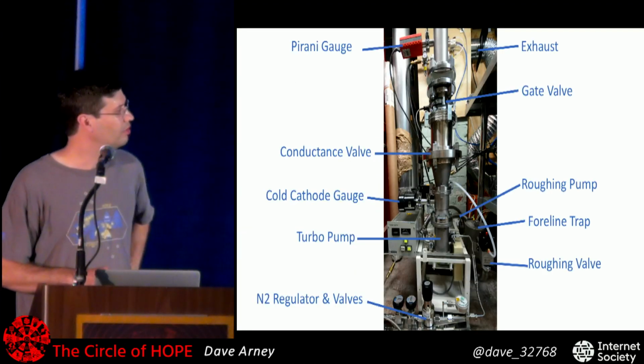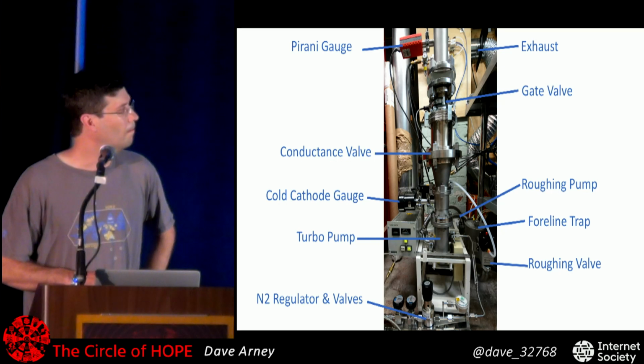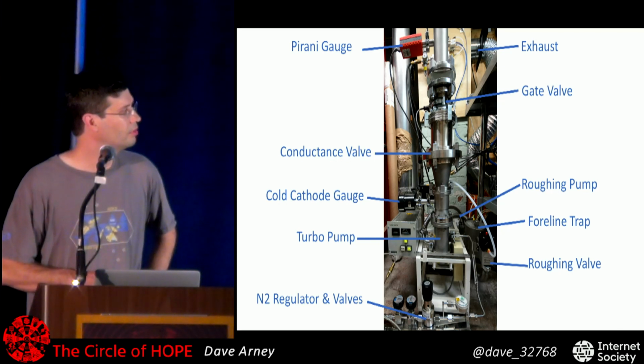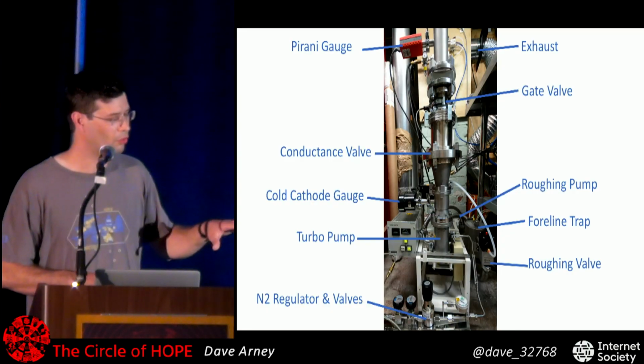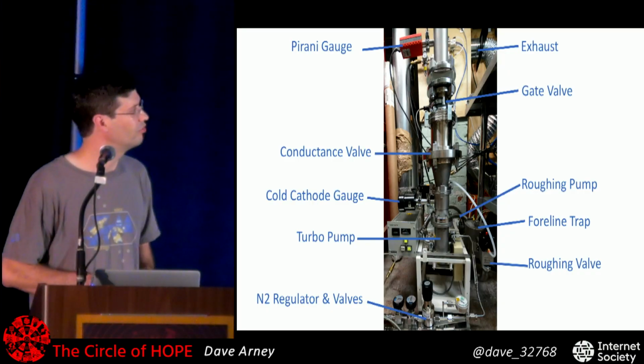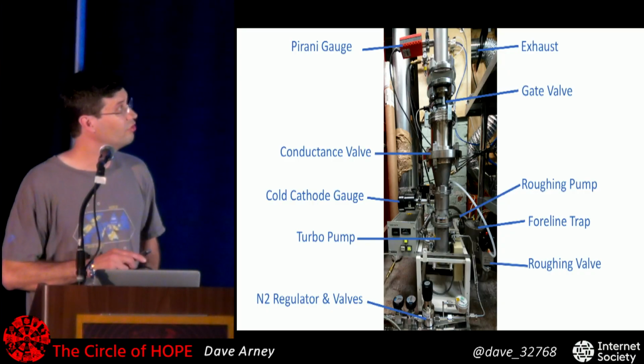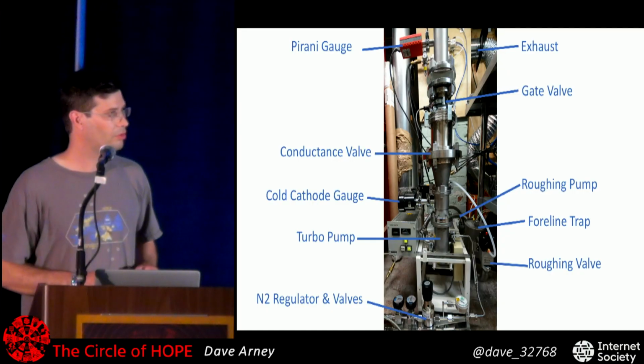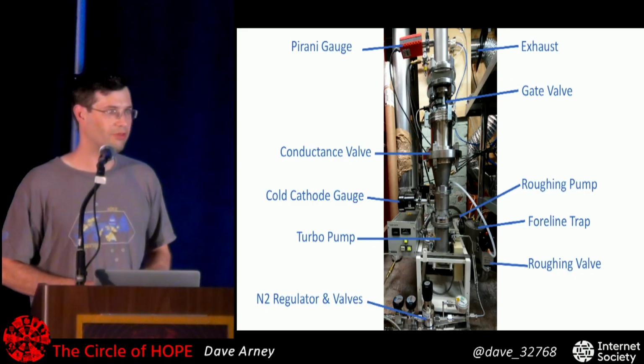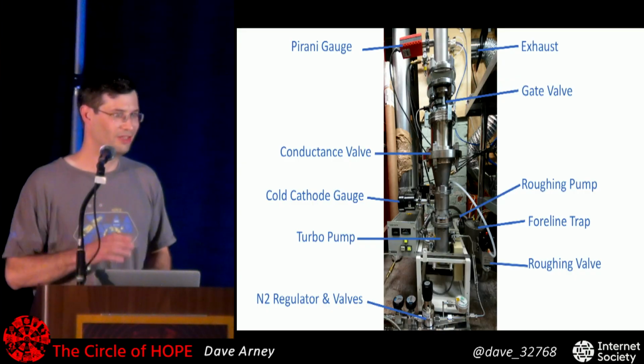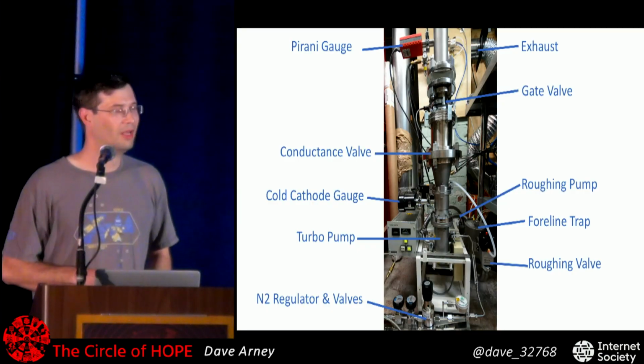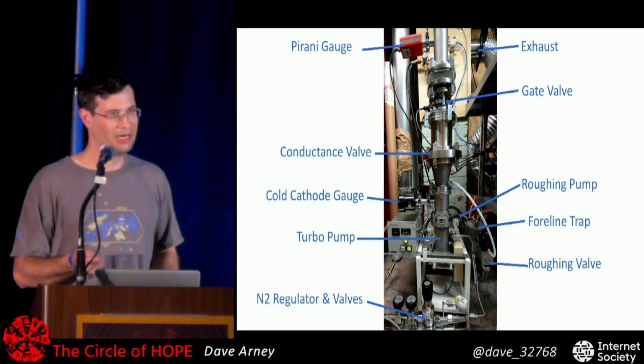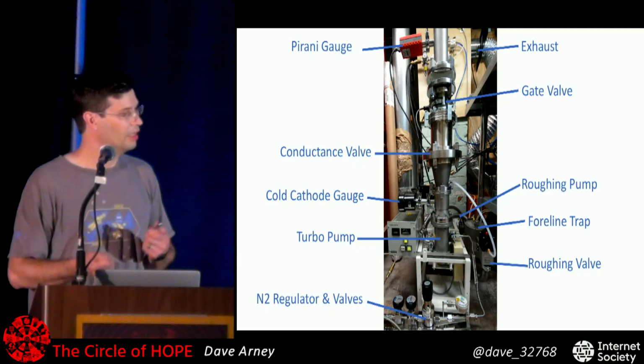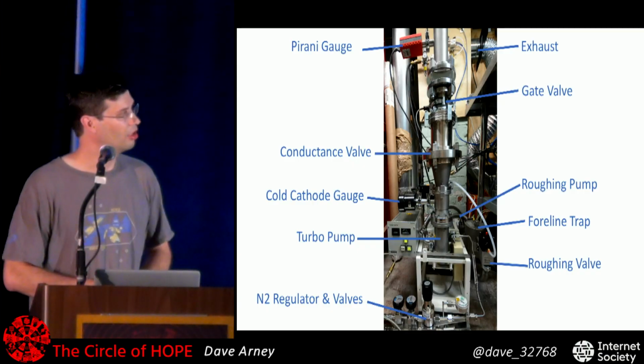Okay, so here's sort of another view with a few more parts. So here's the turbo pump. There's the foreline trap, because the backing pump will release a little bit of oil, and so you want to trap that before it gets into the rest of your system. There's a couple of pressure gauges. If you start working with vacuum, you quickly realize there are a ton of different kinds of pressure gauges. They tend to work at different pressure ranges. Bad things happen if you turn some of them on when they aren't at a good enough vacuum. And so you end up having a bunch of them hung off the system.